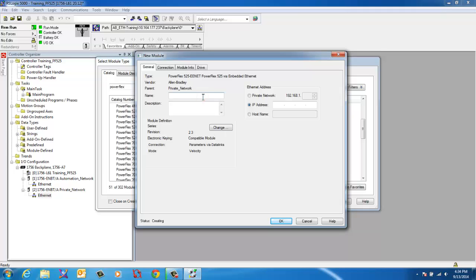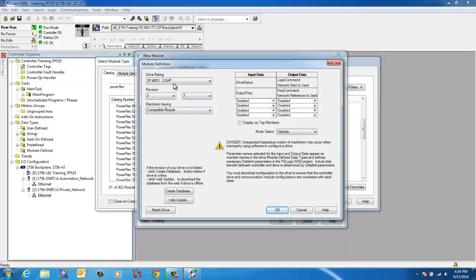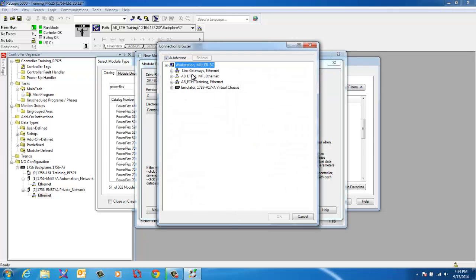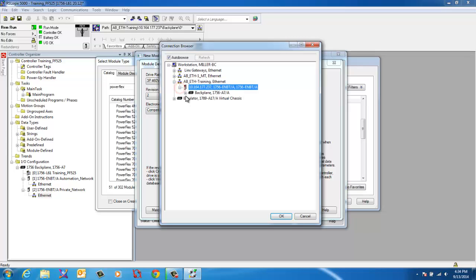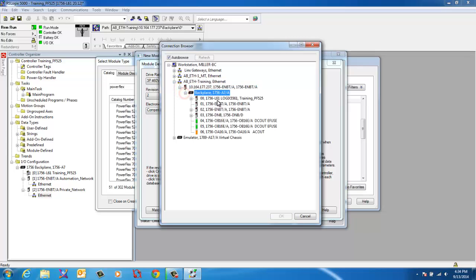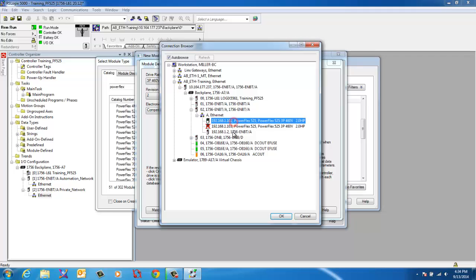It's going to go ahead and give us the newest revision. We'll name this Pump 1. Works for me. Now if we would have discovered it, it would have populated it up here already for you. We know what it is. We'll go ahead and put that in. It was 102. We want to change this. We do. We're going to go online. And what we want to do is we're going to match the drive. So the first thing we'll do is we'll go match the drive. And you'll go into, it'll bring up the RSLinx. You'll pull up where it's at. In training it's under the automation network. Then it's down here underneath your second ethernet card. We have 102. Earlier I had another one in here. We used 102. Hit OK.